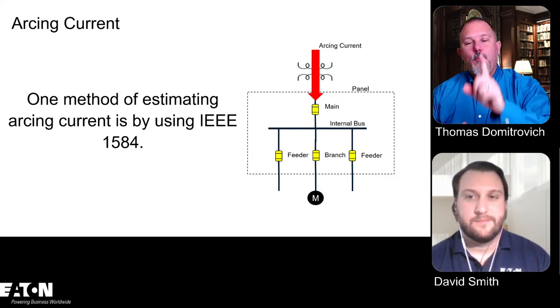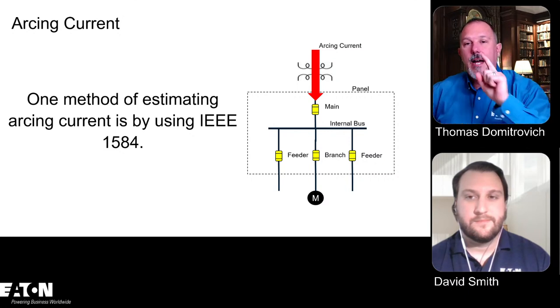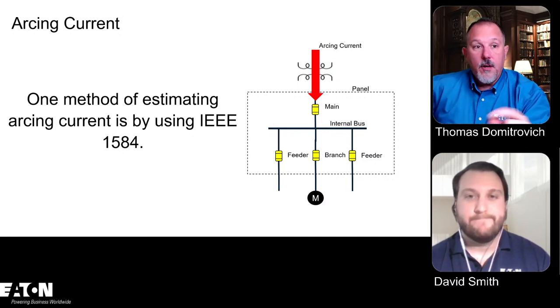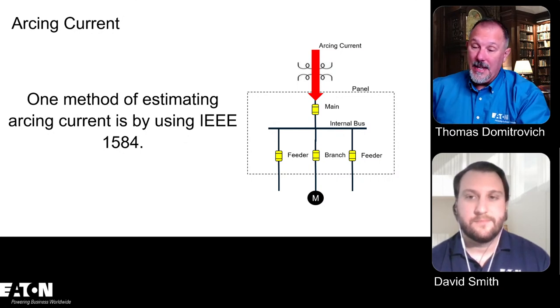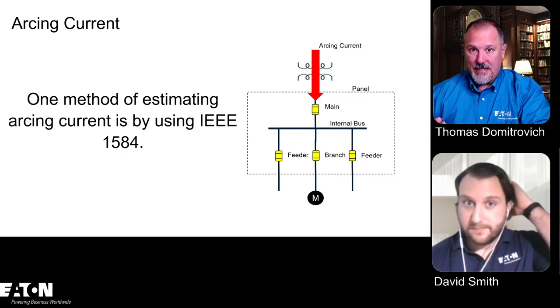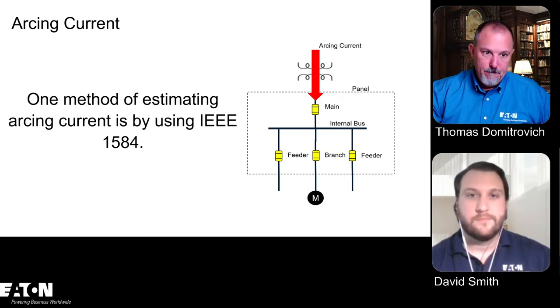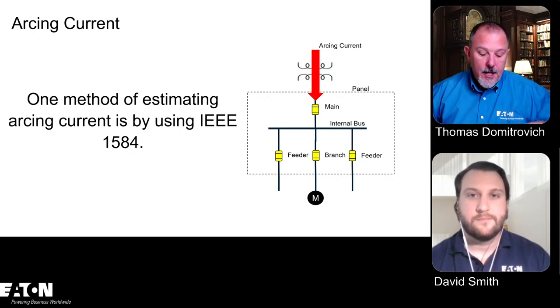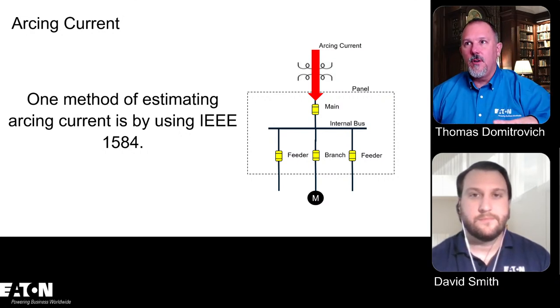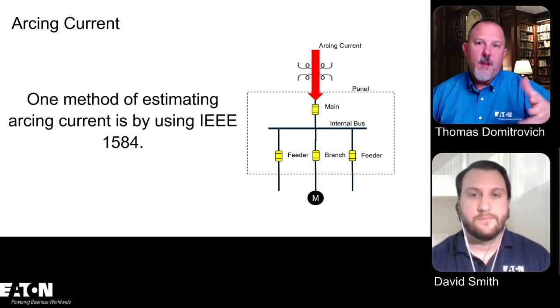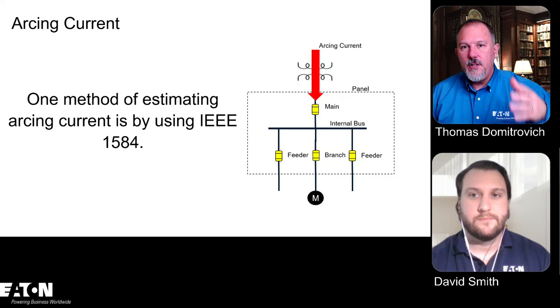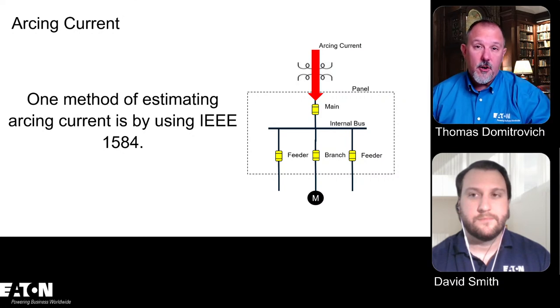It's hard, but what you could say is, I'm going to determine the minimum amount of arcing current. In fact, Ralph Lee doesn't calculate arcing current. Ross, take a look at the IEEE paper from Ralph Lee, and his method does not determine arcing current at all. His method goes straight to incident energy. And the reason I say that, 240.87, here's a challenge or a problem that we have, sort of. 240.87 says you have to compare the arcing current, so that means you have to calculate arcing current.